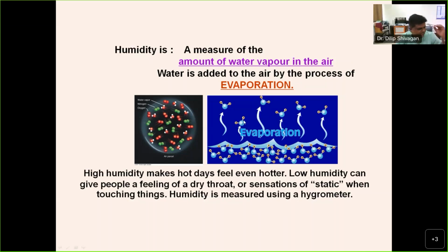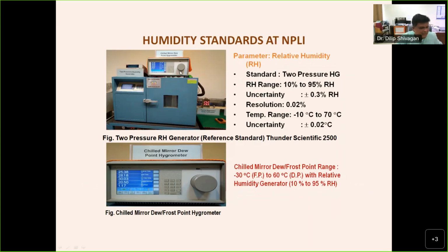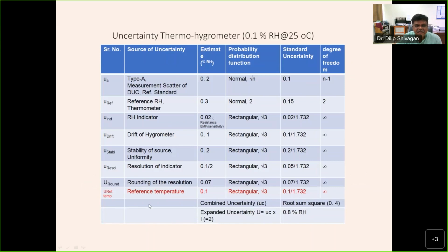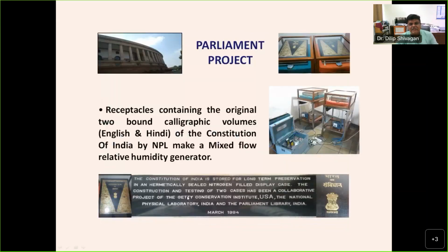Then you can decide this RH to dew point meter, and you can measure the frost and dew. This is our facility, from -30 to 60, for dew and frost. Here only the temperature dependence is very crucial, other parameters can be managed. So you need to have the temperature controlled humidity generator.